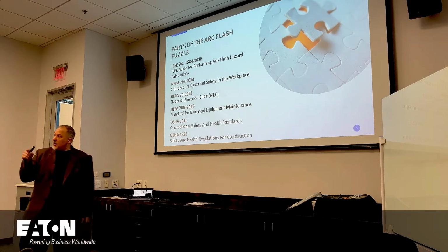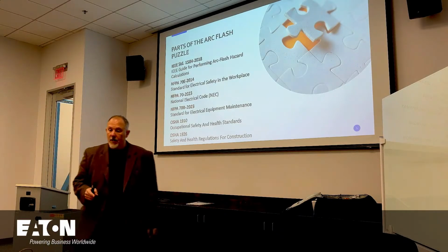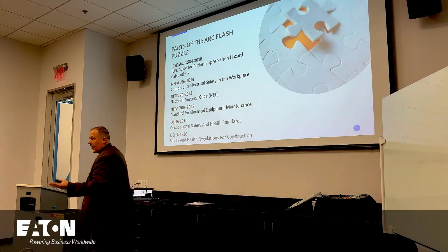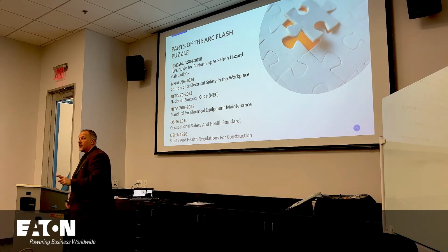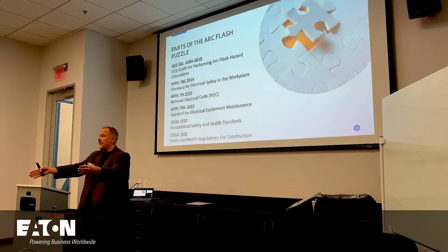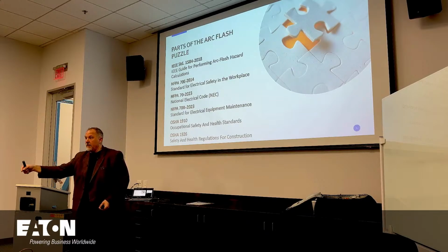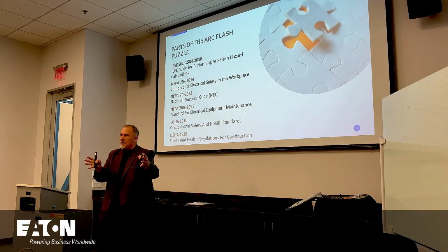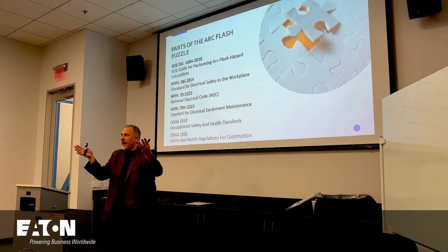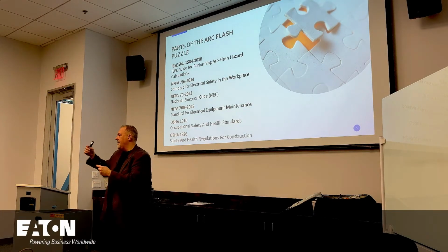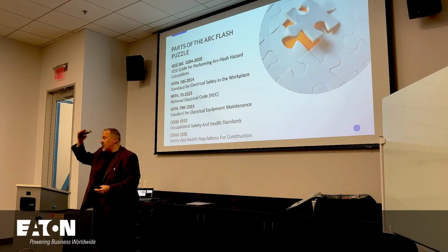So when you look at IEEE 1584 and how we did the testing, we did a box. Here's another argument that I think is very valid and fair: when we went from the 2002 version to 2018, there was a lot of controversy. A lot of people said we shouldn't spend the money on additional testing because nobody who dressed to 2002 came out underdressed.